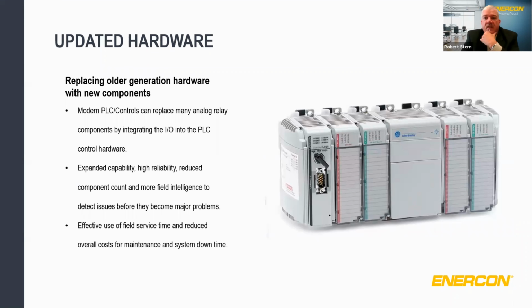Okay, so updated hardware. Going to newer technology PLCs and controls, a lot of analog operators can be incorporated into some newer controls. So you can replace a lot of additional external I/O relays with modern PLC controllers. They're going to give you expanded capability, higher reliability, and reduce component count because you're removing some of those extra I/O operators out there. You're also going to get more intelligence as to what's actually happening with that connected device or even those downstream devices connected to that control panel. And I think you'll be able to utilize your field service teams a lot more effectively because you're going to get more intelligence of what's going on with everything connected. Next page.